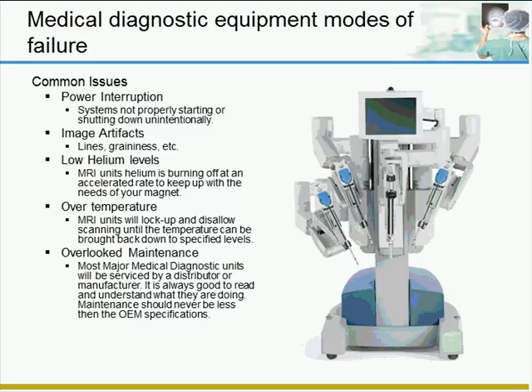Image artifacts, lines and graininess, are typically related to wear and tear. It's a sure sign that maintenance or periodic inspections are due. To catch a potential problem before it gets bad enough to affect the quality, typically you can make repairs during slow periods instead of a failure during the busiest time of the year.